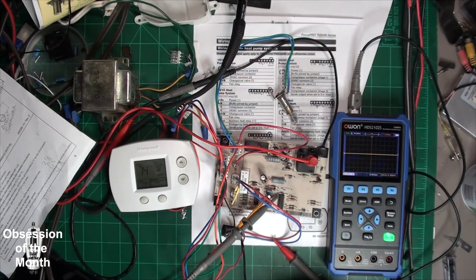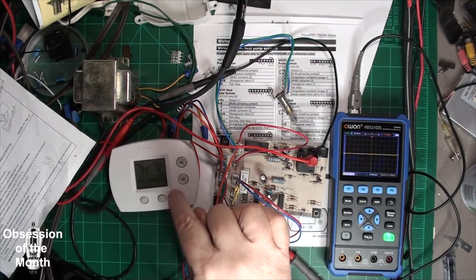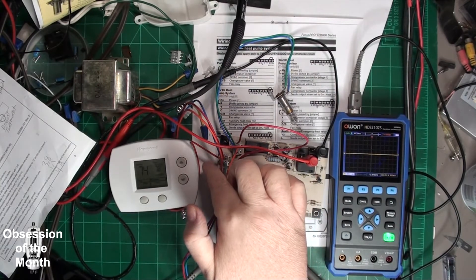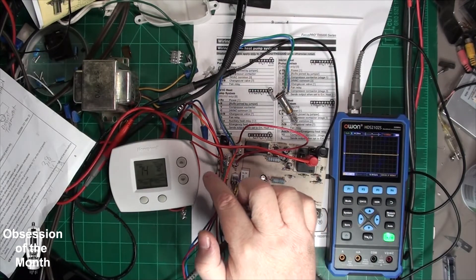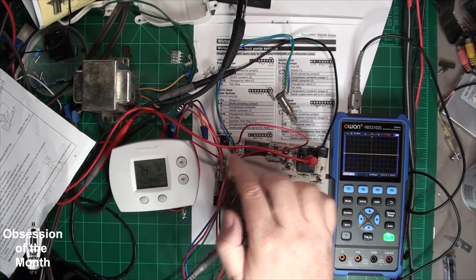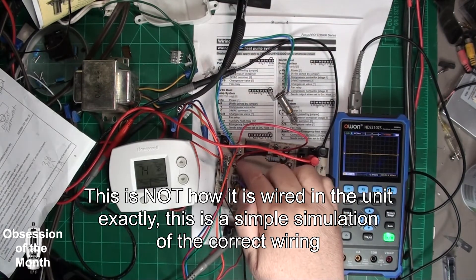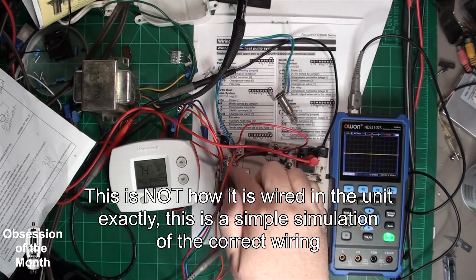The basic gist of this is when heat is turned on, power comes into the R and the Y. And this T1 connection has to receive power. And so I've got the T1 hooked into the Y.